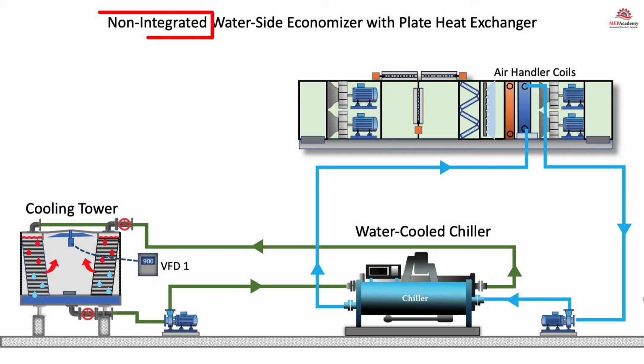Non-integrated waterside economizer. The use of a non-integrated economizer strategy provides for the economizer to be either on or off. There is no simultaneous chiller function. When the economizer is operating, the chiller is 100% off. The condenser water from the cooling tower will satisfy the cooling load without assistance from the chiller. Here we have a water-cooled chilled water plant served by a cooling tower that we can add a waterside economizer to in a non-integrated method, just for you to see the difference.